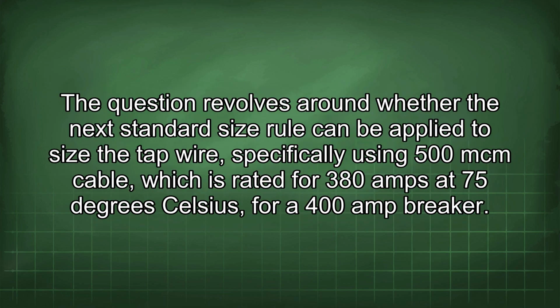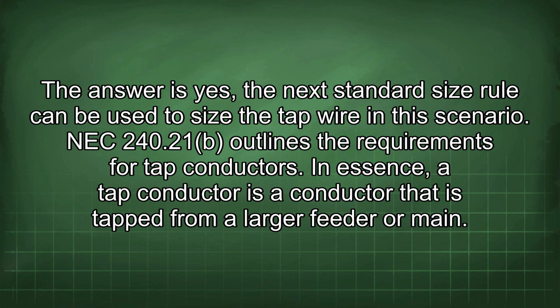The question revolves around whether the next standard size rule can be applied to size the tap wire, specifically using 500 MCM cable, which is rated for 380 amps at 75 degrees Celsius for a 400 amp breaker. The answer is yes, the next standard size rule can be used to size the tap wire in this scenario.